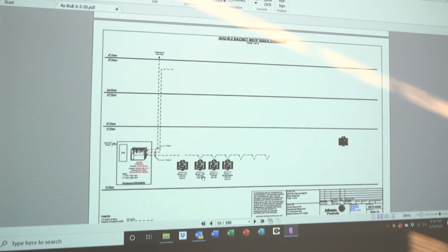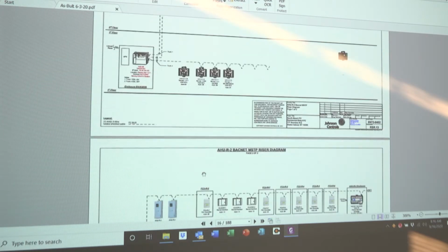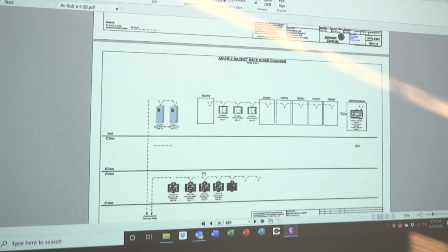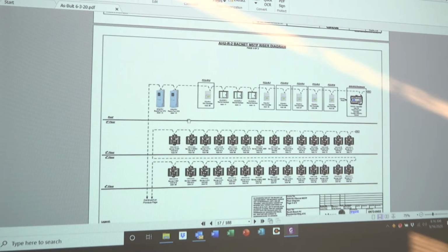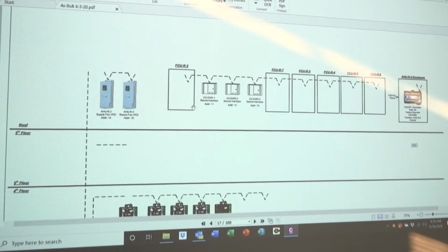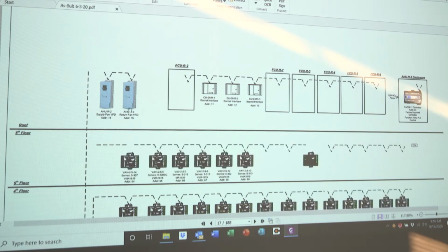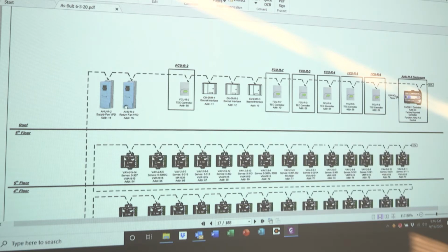We turn the page. We see that sometimes these devices pick up some supplemental equipment. Okay, so this communication link that travels up to the roof level, 6th floor level, you'll notice here that the daisy chain picks up the VFDs for the air handling unit.